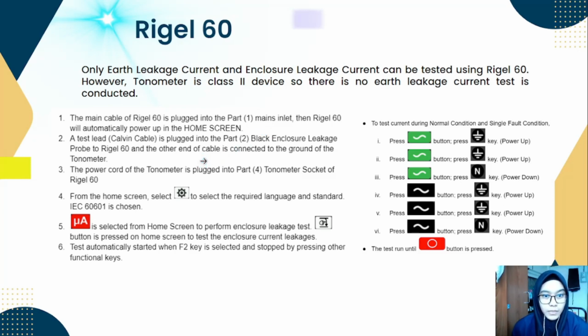Then a test lead is plugged into the part 2 black enclosure leakage probe of the Rigel 60, and the other end of the cable is connected to the ground of the tonometer. The power cord of the tonometer is also plugged into the socket in the Rigel 60. Then, from the home screen, we can select this button to select the required language and standard 60601, because we want to test that one. Then we use this button on the home screen to perform the enclosure leakage current test. This button is pressed on the home screen to test the enclosure leakage current.